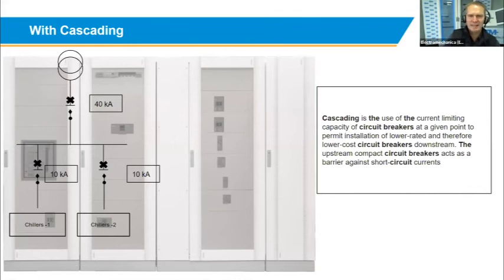So by using proper cascading, what we're saying is that in this board that's rated 40 kA, you can actually put a 10 kA miniature circuit breaker inside this board. And the way the cascading then works is that if a short circuit does appear in the feeder for chiller number 2, instead of opening this product, the main incomer will open and protect your whole distribution board. Yeah, you might lose power to the whole board, but at least the cost in doing this is a lot lower than trying to do a fully rated distribution board.